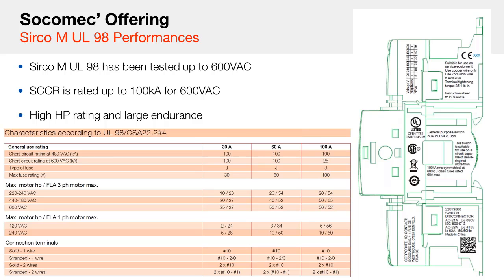So here you can see the characteristics for this Socomec UL98. It is also tested up to 600 VAC, and it was tested to achieve a high fault short circuit rating of 100 kA. So you can see it has that higher short circuit rating. It's also HP rated, and the switch characteristics can always be found in our catalog pages or on the side of the switch that you can see on the right-hand side of the screen. All these characteristics are also posted on the switches as well.